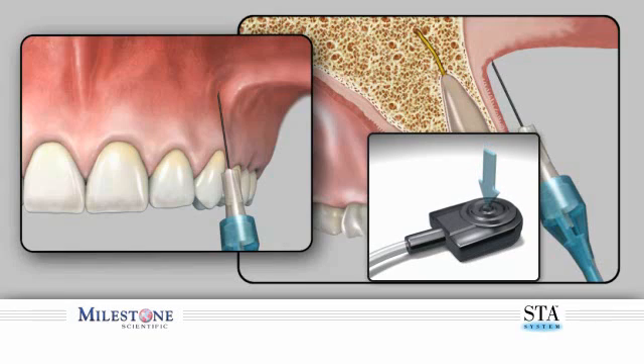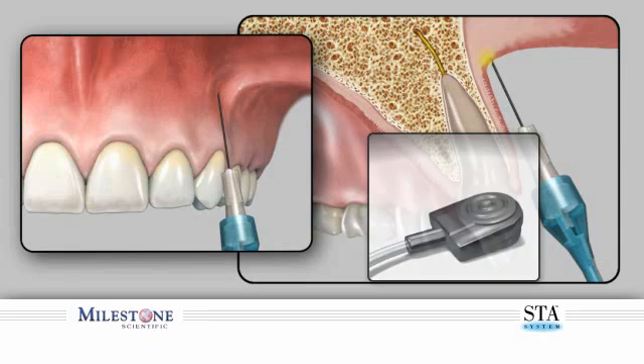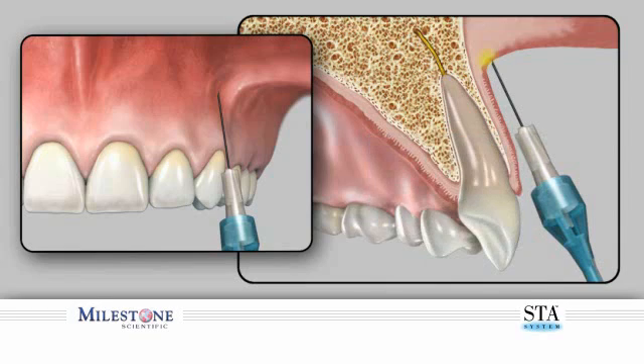After three beeps, the STA system will announce "cruise." Upon hearing the cruise announcement, remove your foot from the foot control pedal if you desire to use the cruise feature. This begins the anesthetic flow to the injection site.